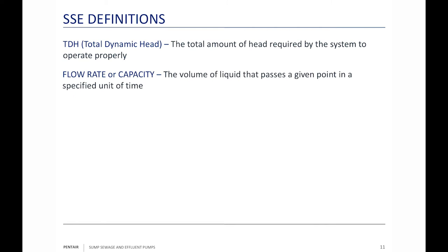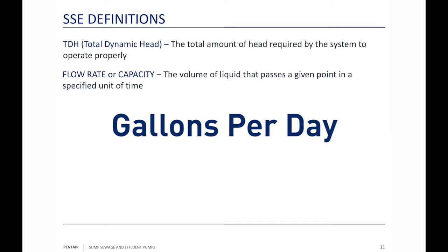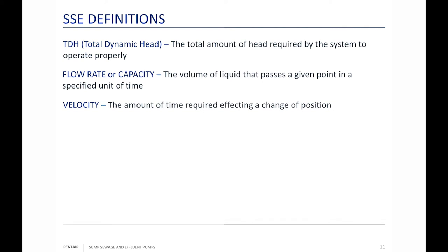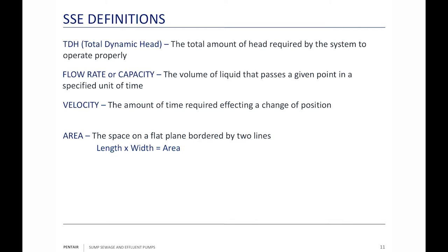Flow rate or capacity is the volume of liquid passing a given point in a specified amount of time — we use gallons per minute. In SSE we also use gallons per day because the inspector tells you how many gallons per day per square foot you can put into the leach field, which helps size it. Velocity is the speed of the water moving through the piping system. Area is a space on a flat plane — for a leach field it's length times width; for a pipe it's pi r squared, or since we talk in diameters, ID squared times pi divided by four.